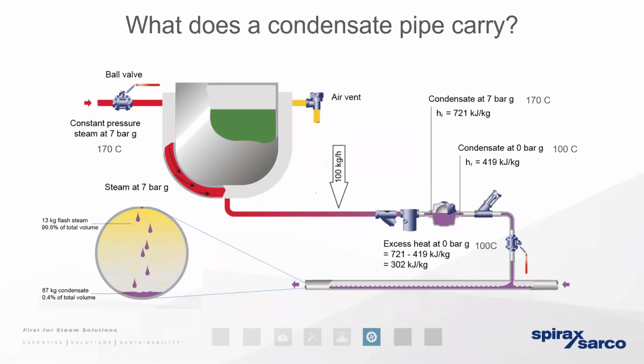If we've got a steam process that is condensing steam at a high pressure because it requires that high temperature, the example we've got here, 7 bar gauge, where we know that steam exists at 170 C. When steam gives up its energy and condenses, that condensate is now a liquid. It's given up its latent heat. It retains the sensible heat. But the temperature of the condensate at 7 bar gauge is 170 degrees, the same as steam.